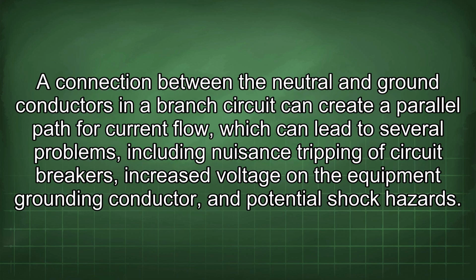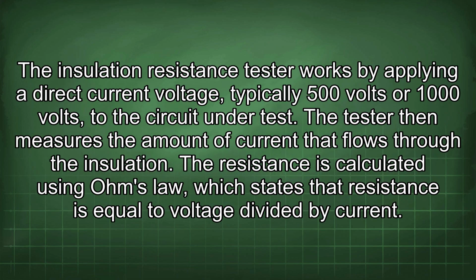A connection between the neutral and ground conductors in a branch circuit can create a parallel path for current flow, which can lead to several problems, including nuisance tripping of circuit breakers, increased voltage on the equipment grounding conductor, and potential shock hazards. The insulation resistance tester works by applying a direct current voltage, typically 500 volts or 1000 volts, to the circuit under test.